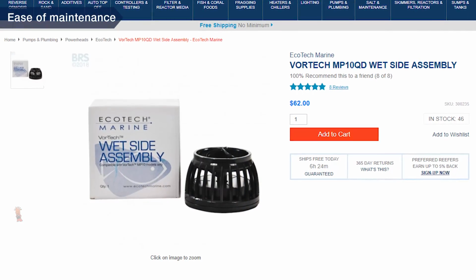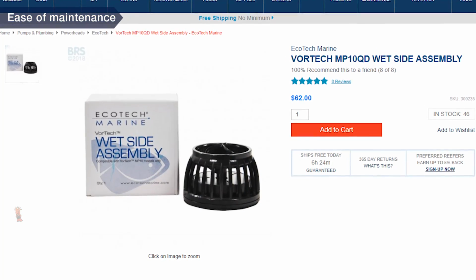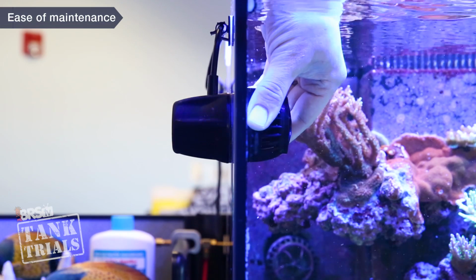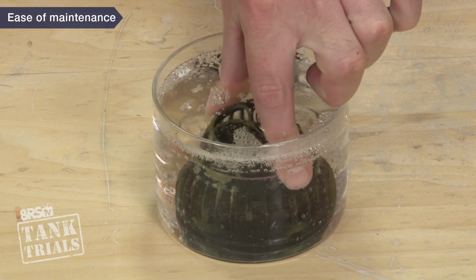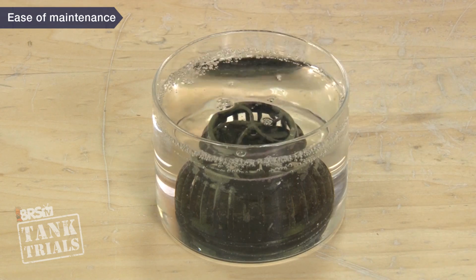Many reefers will actually pick up a pair of extra wet sides, so pump maintenance takes all of 10 seconds. Pull out the dirty one and replace with a clean one, then just soak the dirty ones for next time. This is obviously a pretty attractive solution.